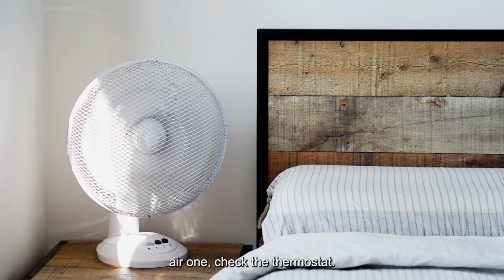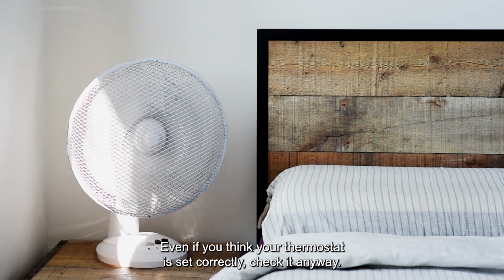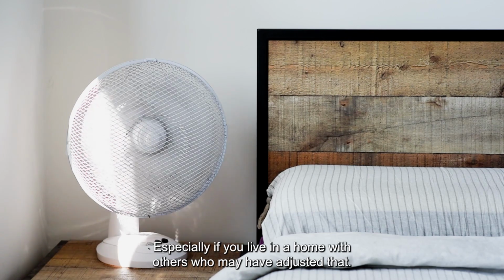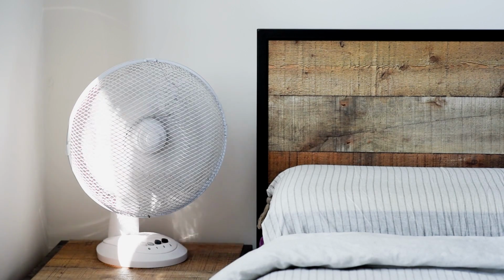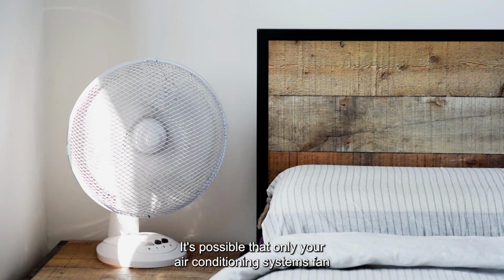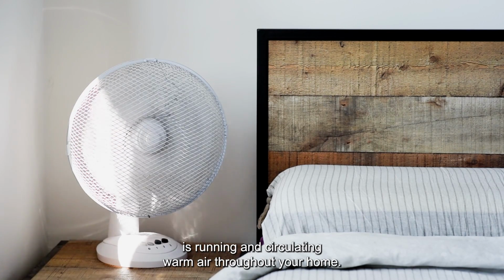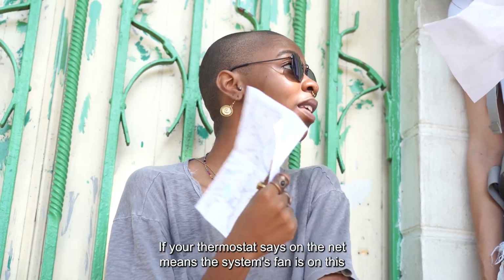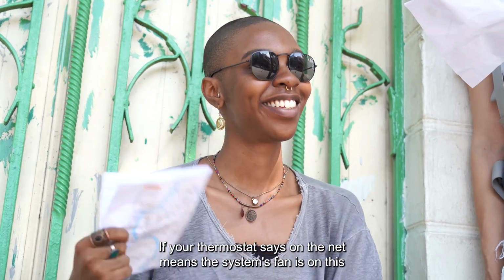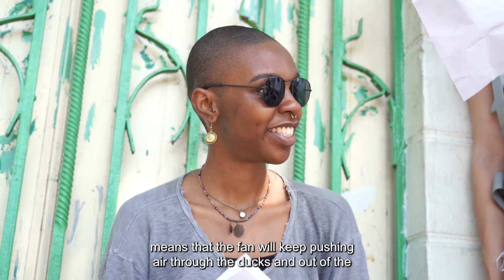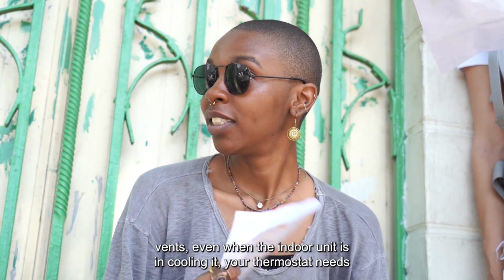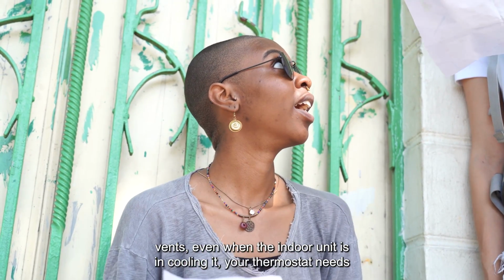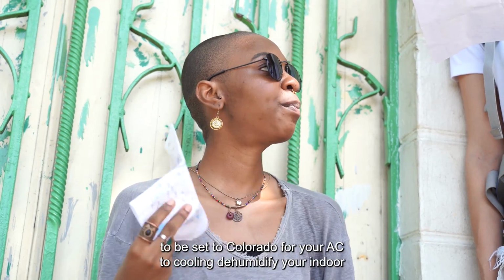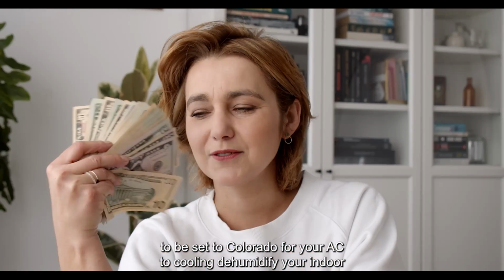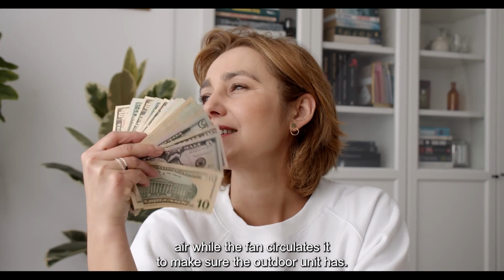1. Check the thermostat. Even if you think your thermostat is set correctly, check it anyway, especially if you live in a home with others who may have adjusted the thermostat. It's possible that only your air conditioning system's fan is running and circulating warm air throughout your home. If your thermostat says "on," then that means the system's fan is on. This means that the fan will keep pushing air through the ducts and out of the vents, even when the indoor unit isn't cooling it. Your thermostat needs to be set to "cool" or "auto" for your AC to cool and dehumidify your indoor air, while the fan circulates it.